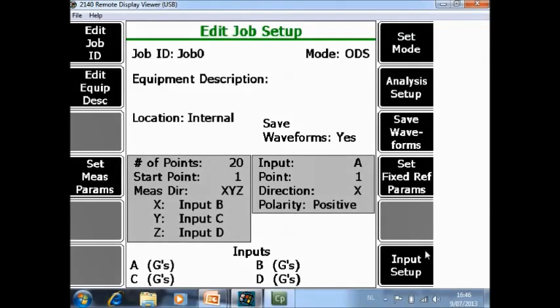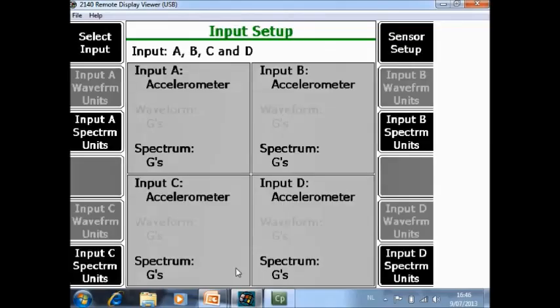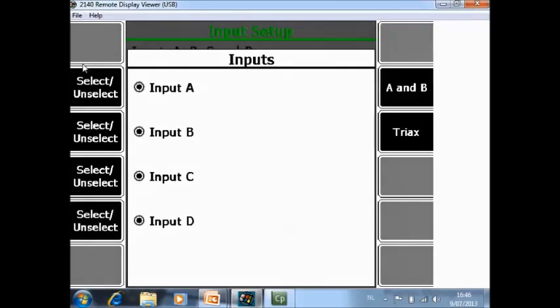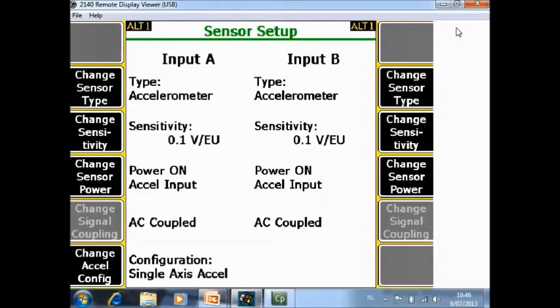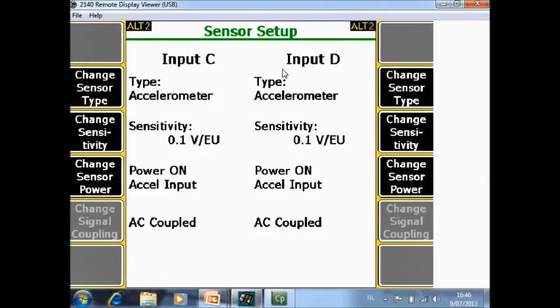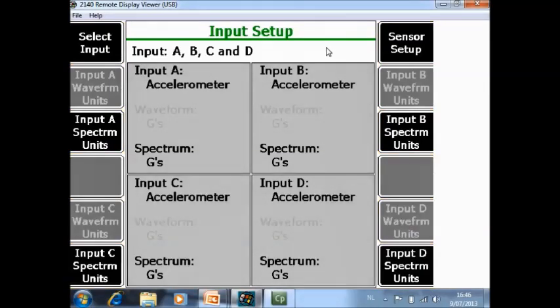And last input setup. Here you can specify the sensors that you use for your ODS or modal job. Input setup, select input. As you can see I have activated the four channels and everywhere I have an accelerometer. If that is not correct you can check it here sensor setup. I have on channel A, B, C and D an accelerometer. And if you want to see the result in velocity you can change it here.